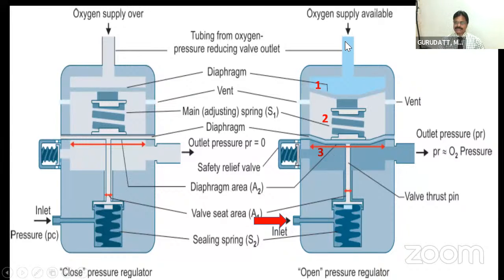As long as the oxygen pressure is there in chamber 1, it is going to depress the diaphragm between chambers 1 and 2. In turn, the spring gets activated. It is going to depress the diaphragm between chambers 2 and 3. That in turn is going to depress this valve thrust pin. Once the valve thrust pin is depressed, the nitrous oxide can flow into chamber 3 and flow out. This is how the master-slave mechanism works. If the oxygen pressure is not there, the valve thrust pin will totally block the flow of nitrous oxide into chamber 3, and there won't be any outlet of the nitrous oxide. That's how the master and slave mechanism works.